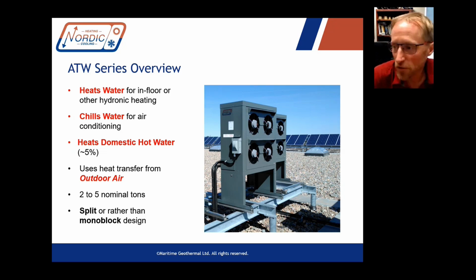It's not that it doesn't work in colder places; it's just that it would require that much more backup heat, and the capacity would be that much more reduced. It would spend more time running at its minimum temperature. These units run the compressor down to as cold as -22 Celsius outside. Below that temperature, your backup heat needs to take over the whole load. So with an air source heat pump, you have to size the auxiliary heat, or the backup heat, for the coldest day heat load, because even if it rarely ever gets there, you have to have that possibility covered.